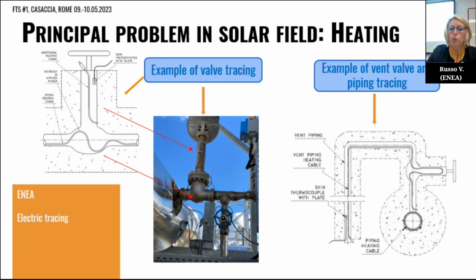Here is an installation in a real plant. Here instead there is a scheme of the tracing of the vent valve and the relative piping. In this case, the vent piping must be traced for all the length, because even if some salt goes out from the vent valve, the salt doesn't freeze, and so doesn't block the vent line.